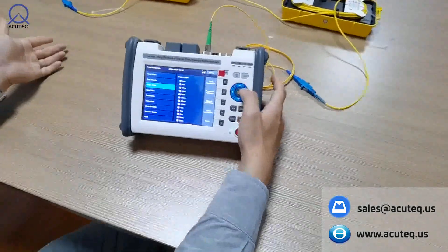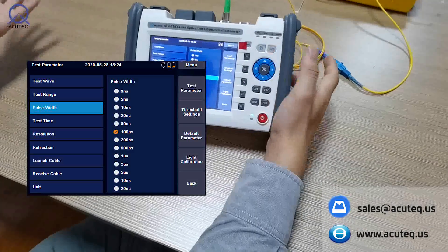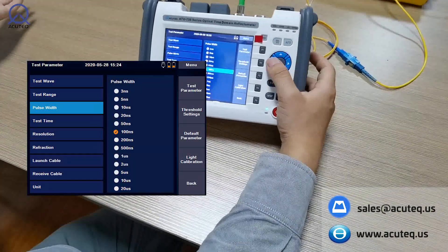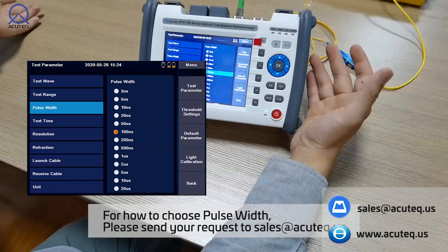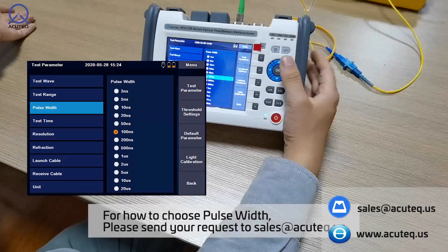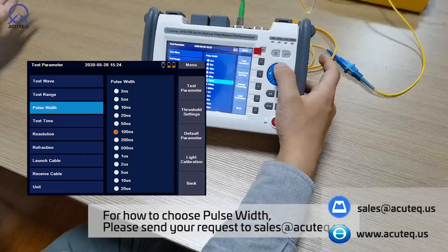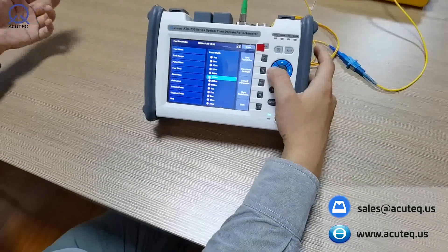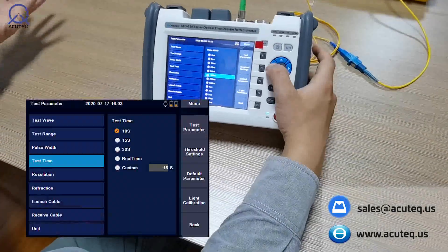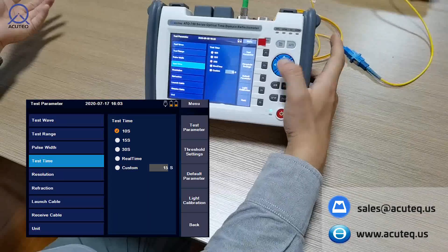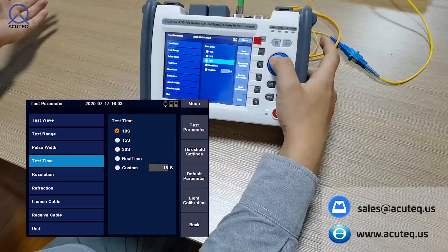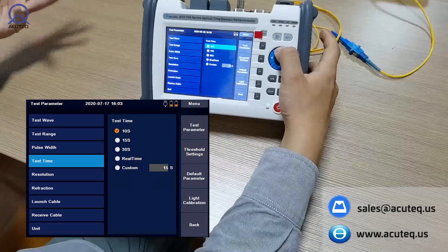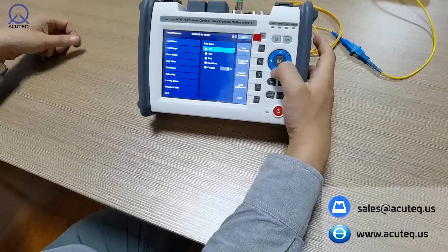For pulse width, you can choose about 100 nanoseconds since this is a 42dB dynamic range OTDR — you can even choose 50. We'll choose 100 just to explain it better. For testing time, you can choose 30, 15, or 10 seconds. We'll choose 10 just to demonstrate it.